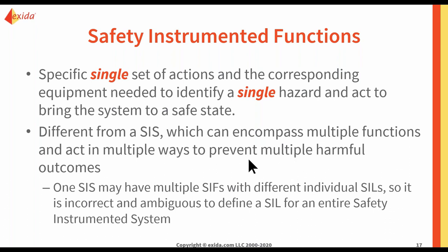And a SIS can encompass different kinds of functions. So as I've mentioned before, one SIS can have multiple SIFs with different individual SILs. So remember, it is always incorrect to say that you have a SIS of one single SIL, because a SIL is attached to each of the SIFs. Instead, a collection of different SIFs is going to contribute to a whole SIS.